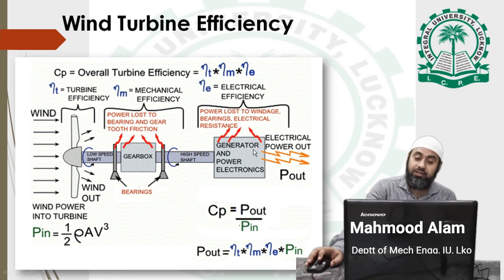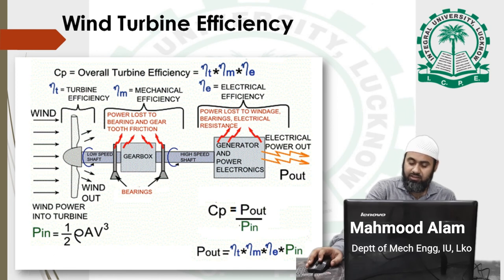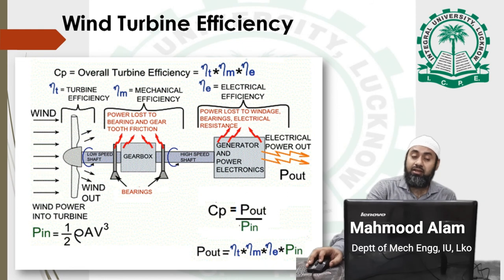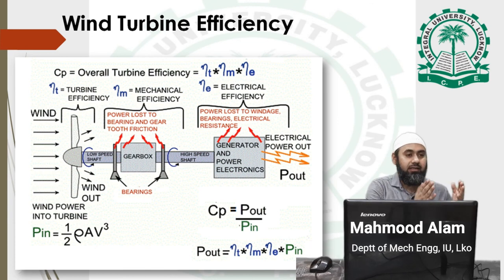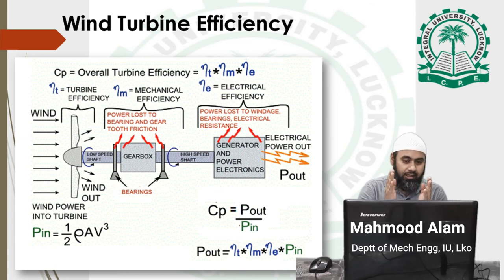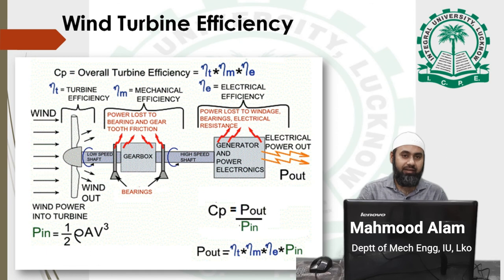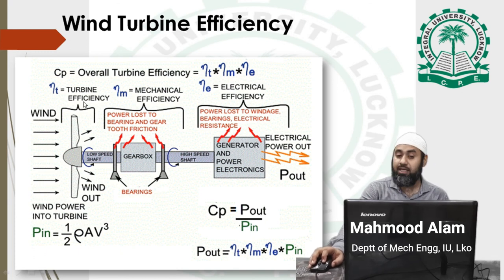For the electrical generator efficiency, the generator also has various losses — windage losses, bearing losses, and electrical resistance losses. The electrical efficiency is calculated as the power output, meaning the electrical energy generated, with respect to the total mechanical energy available at the inlet of the generator. This ratio is known as the electrical efficiency of the generator. So the three efficiencies are: turbine efficiency, mechanical efficiency, and electrical efficiency.